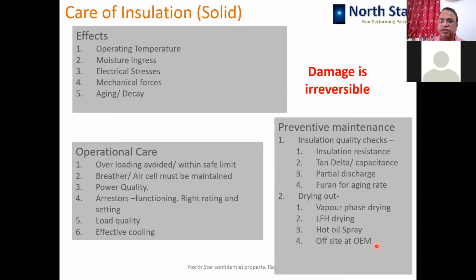So all these tests, depending upon the transformer type, have to be performed so that you know where your transformer insulation is standing. And then drying out can be practiced. Drying out is different from oil filtration. Oil filtration does not necessarily dry out the solid insulation.